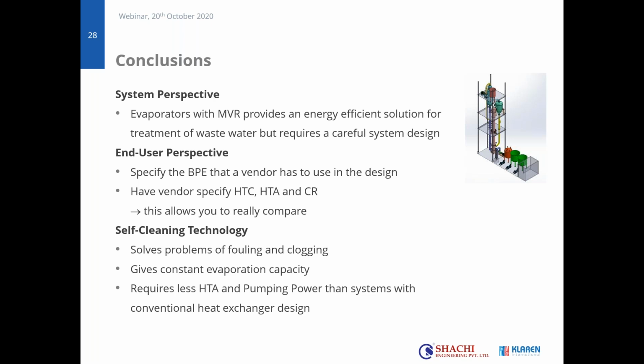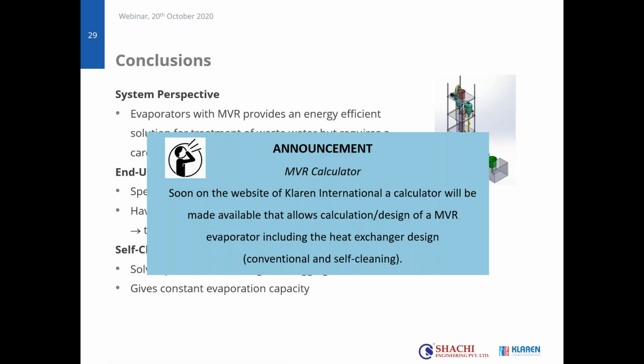Maybe, by the way, a last remark. I forgot about that, and a short announcement from our side. We're working on an MVR calculator, in which you can simply fill in what feed you have, the inlet concentration and outlet concentration, what temperature you want the MVR to run on, and whether you want a conventional heat exchanger or a self-cleaning one. It will calculate how much power to use, what the energy cost is, and how big the heat exchanger has to be. You can use that for your own understanding, to evaluate vendors, or to have a discussion with us. But just as a courtesy from our side to assist you.